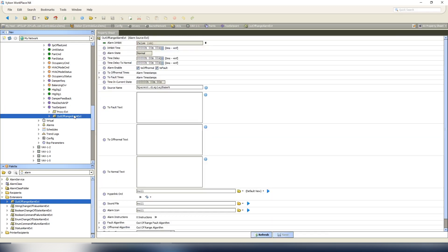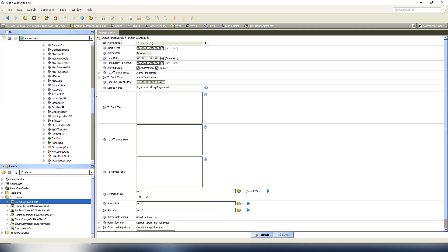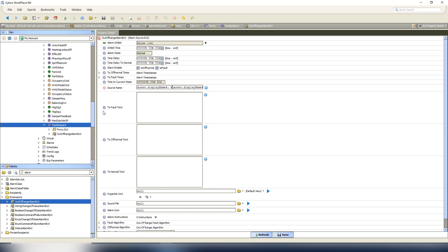Let's configure our options. Our out of range alarm is here. So for the source name, parent dot display name is going to say test set point, but we want to be more specific and tell it what VAV box it is. So that's two levels ahead of it, so we're going to do parent dot parent dot parent dot display name colon, and I'll put a space. So now the source name will read VAV 1-1 colon space test set point.